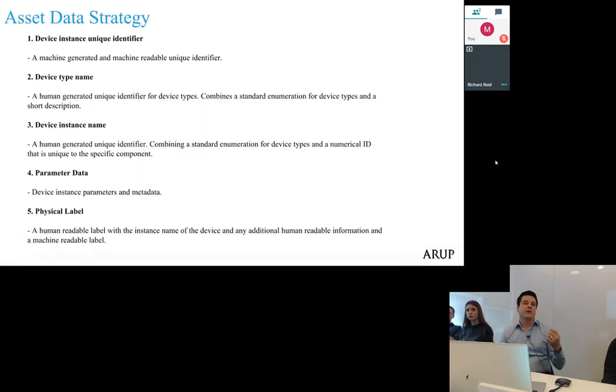So our asset strategy first, and then I'll come on to the point strategy for British Land, is that every device must have a unique identifier, and that's a machine-readable label. So an individual would not understand what that machine-readable label means. Then we have a device type name, an instance name, parameter data, and physical label. I'll talk through each one of these steps now.